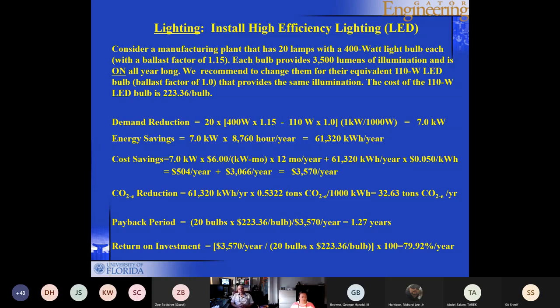So what we do is we recommend to change these for their equivalent 110 watt LED bulb. The LED bulb is a more efficient light bulb. It has a ballast factor of 1. It provides the same amount of illumination, but of course it's 110 watt instead of 400 watts. The cost of a 110 watt LED bulb is $223 per bulb. So it's not cheap, but hopefully you will be able to recover the cost over time.